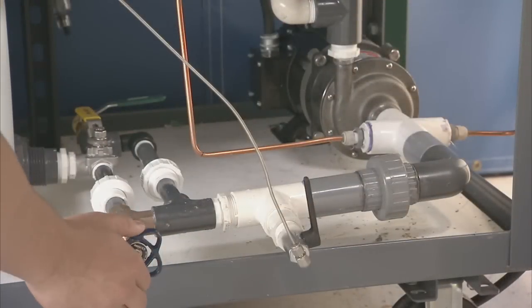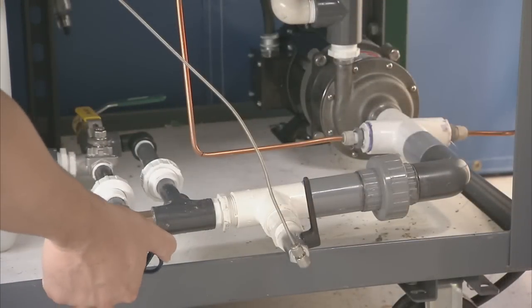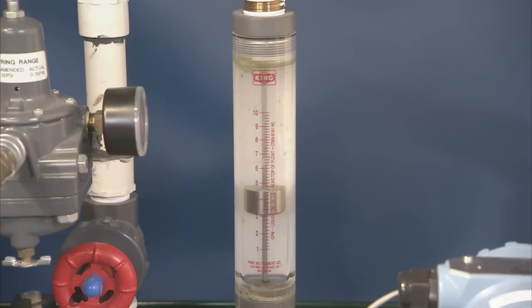To demonstrate this, I will slowly close this valve here. This controls the flow of water to the pump. I will restrict the flow until the cavitation occurs.